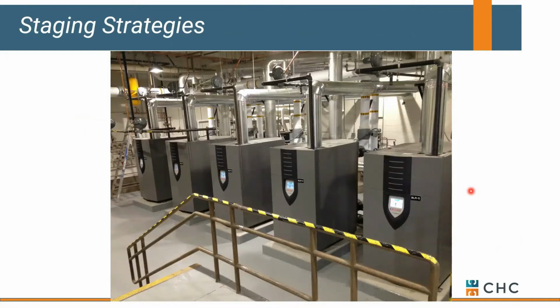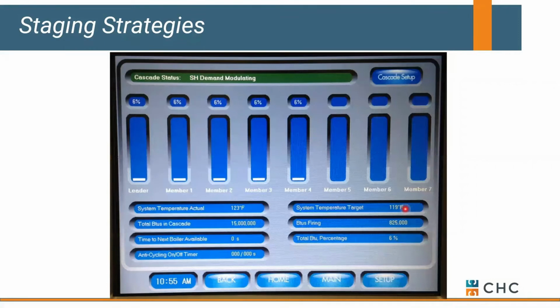Let's talk about if you've got multiple boilers in your plant and they happen to be condensing, how would you stage those? Would you bring one boiler on at 100% and then bring boiler number 2 on until it got to 100%, then bring boiler 3 on and 4 and 5? That's what you might think, but since they're condensing boilers, it makes more efficiency sense to fire them all at low fire, okay? Might be a little counterintuitive, but when you're dealing with condensing boilers, remember they're most efficient at low firing rate.